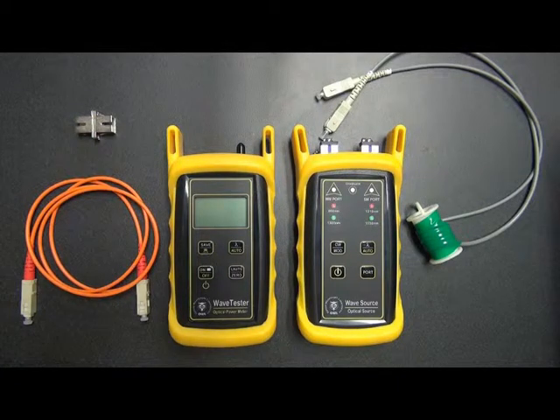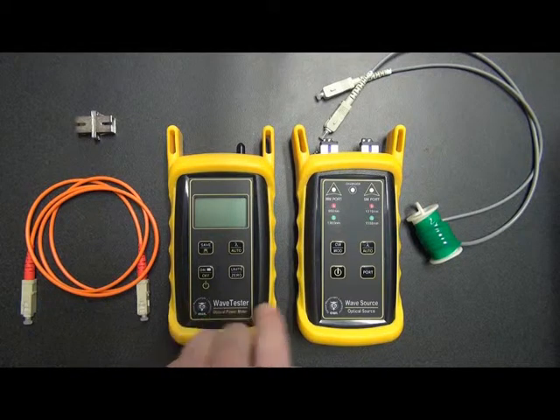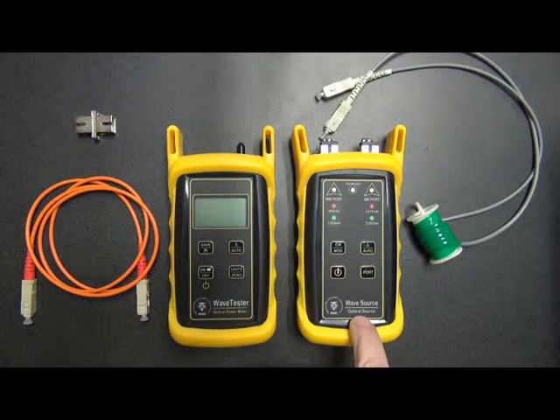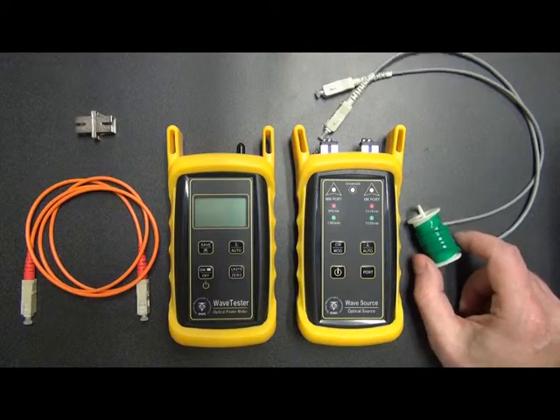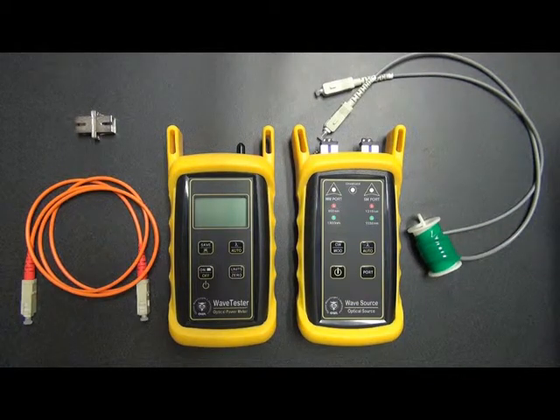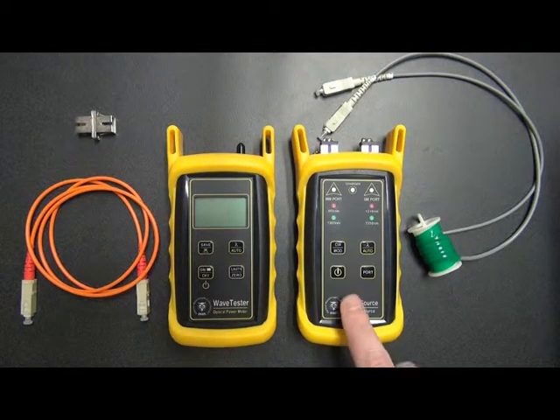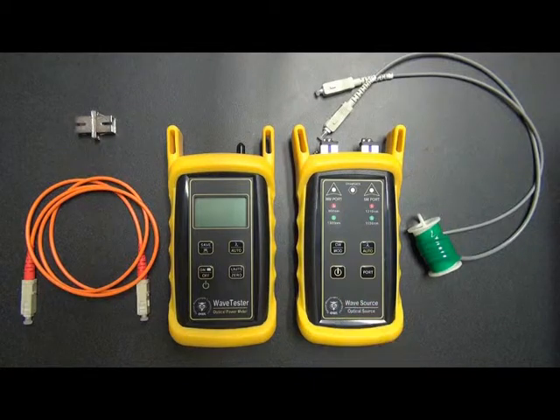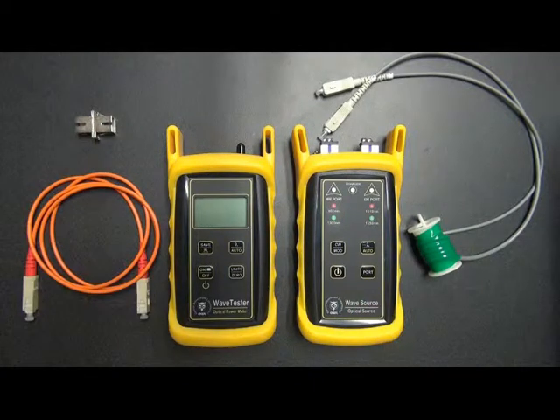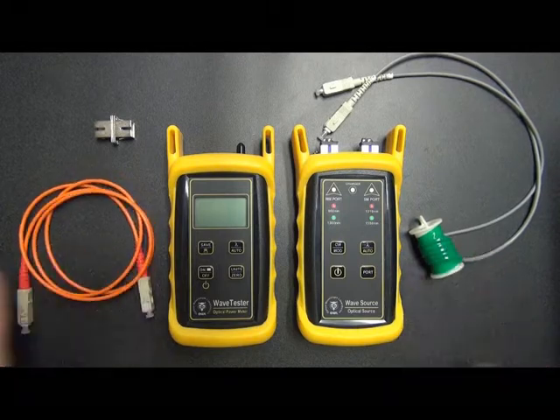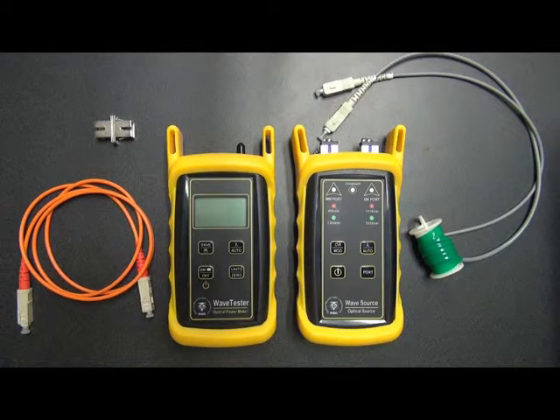In this procedure, we will be using the WaveTester Optical Power Meter and the multimode port on the WaveSource optical light source. You'll notice that there are two patch cables and one mating sleeve used in this procedure. Since this is multimode, one of the reference cables is wrapped around a mandrel per testing standards. The mandrel wrapped reference cable will be used to zero out the test equipment as well as connect the WaveSource into the link under test. The second cable is used to connect the WaveTester into the link under test. And the mating sleeve is just used for this procedure only to connect these two cables together for the purpose of making sure that they're working fine.